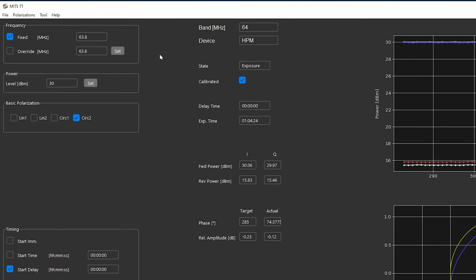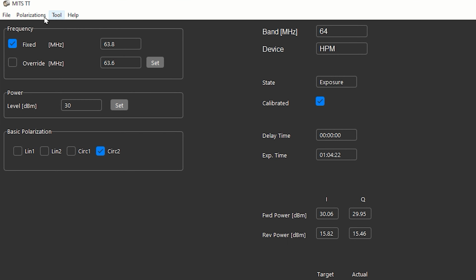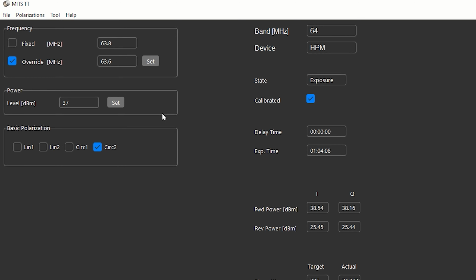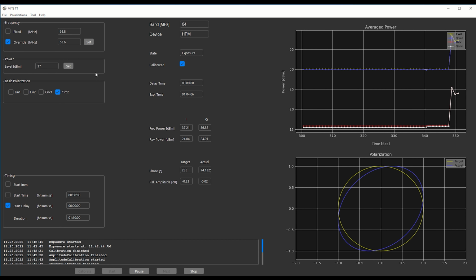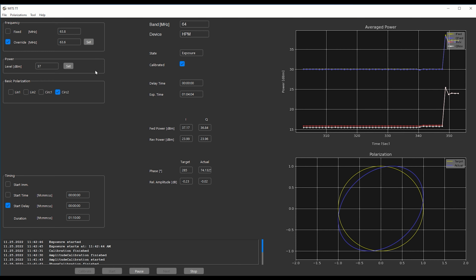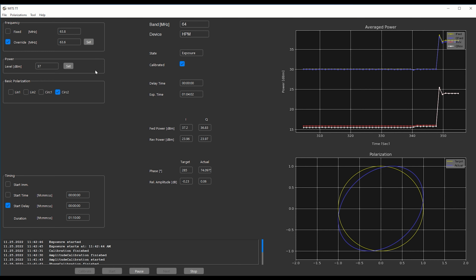Now that we started our software, we can see here in the top left our frequency of operation, which you can override with a custom frequency. Underneath is the input of the power level. The maximum is 40 dBm, which results in generated E fields of about 60 volt per meters in the high permittivity medium. This is sufficient to perform validation with sensitive dosimetric and temperature probes.